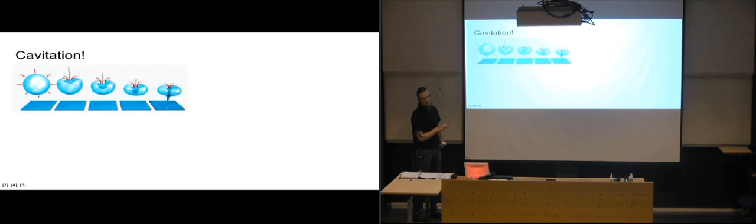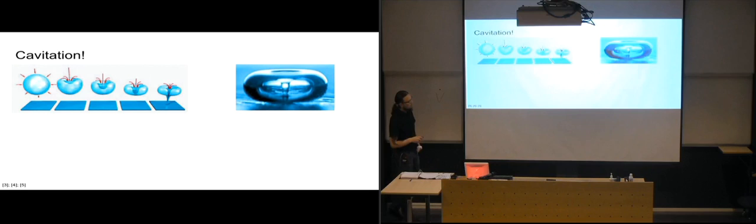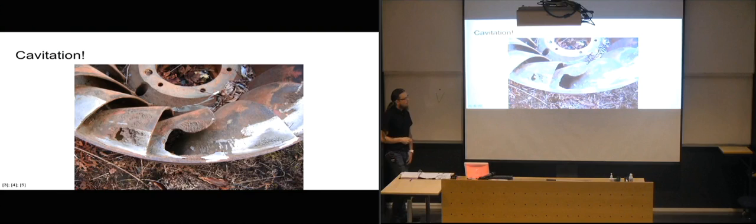So it's pretty effective. And here you actually see a very good picture of one of these bubbles as it is about to collapse. So you've got this tunnel through the bubble. That is right before it's bursting. And this is an impeller, a propeller type of thing. And all of this damage is not corrosion. Everything is cavitation. It's just been blasted apart by the cavitation.